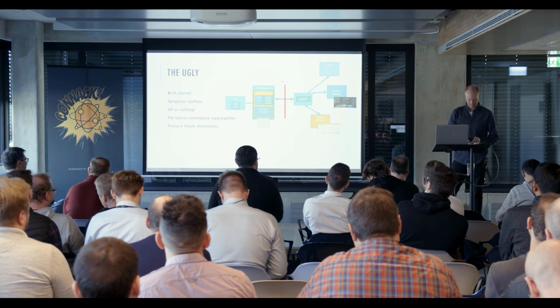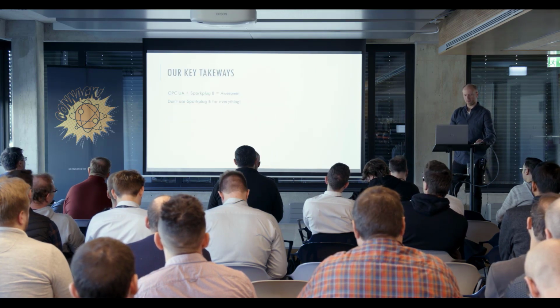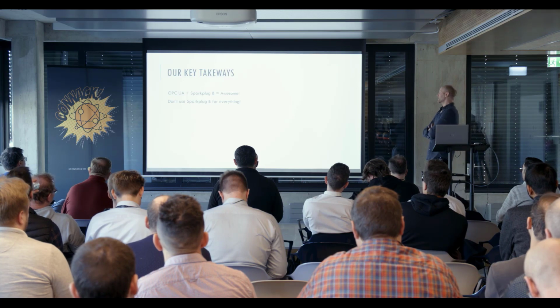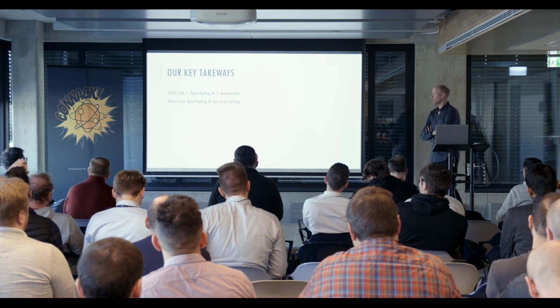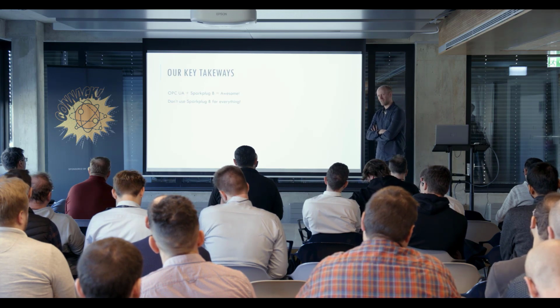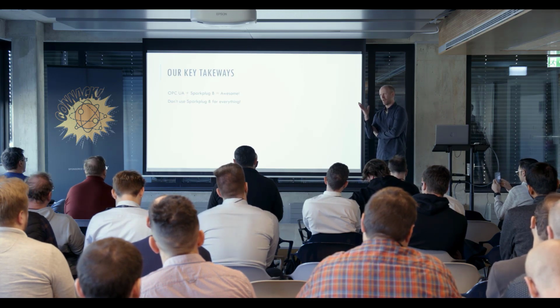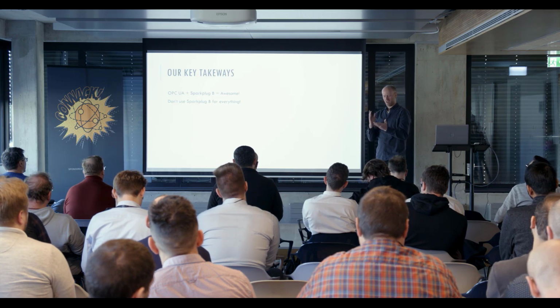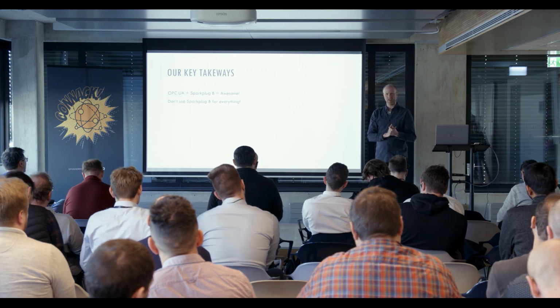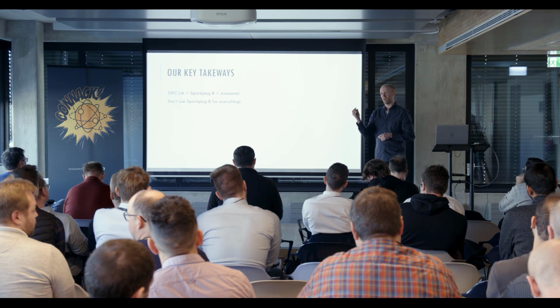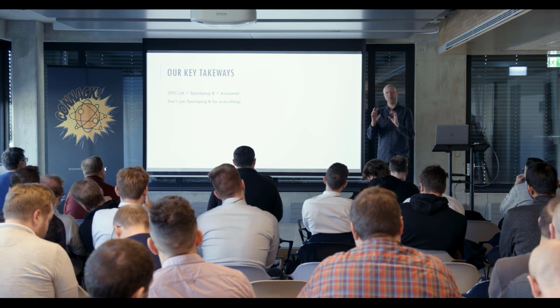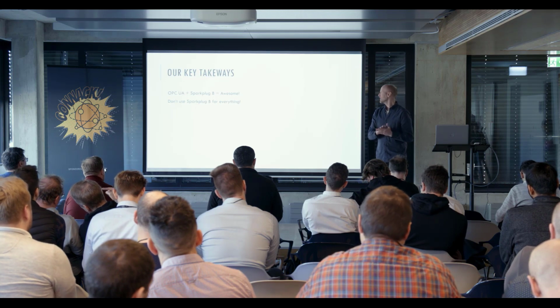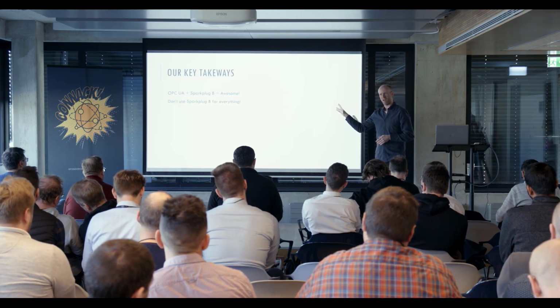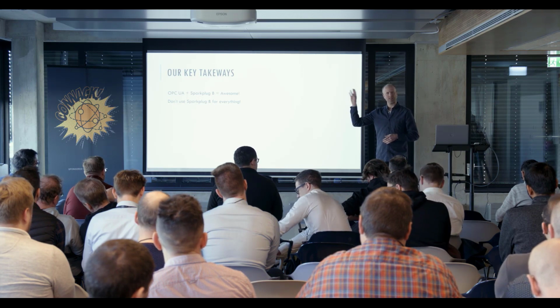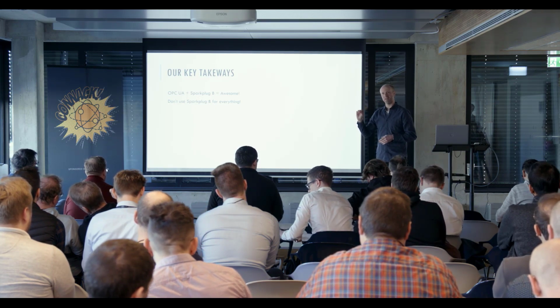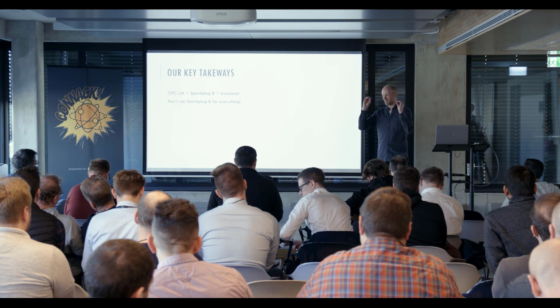So that's the ugly. To summarize, our key takeaway is that OPC UA plus Sparkplug B is awesome. We have OPC UA on the edge, meaning I can control how fast I sample and select the data I want to collect. So I get the control of OPC UA on one end, but also the simplicity, the plug and play, the UDTs, templates, properties, and metadata I want from Sparkplug B. Combining these two, I think, is great.